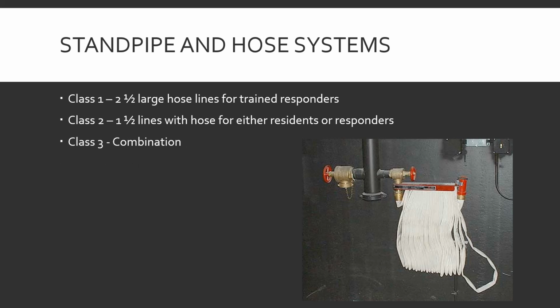Standpipes and hose systems. Class 1 systems. 2.5s. I looked this one up. This one's in the book. But they're all 2.5 sized or potentially even larger hose lines for trained responders. These are the ones that don't have the little fire hose station like the picture here or the little case on the wall with the fire hose in it. It's just a couple valves on the wall. Fire department shows up, we connect our hoses to them because we're trained to use the large, high pressure 2.5 sized hoses.